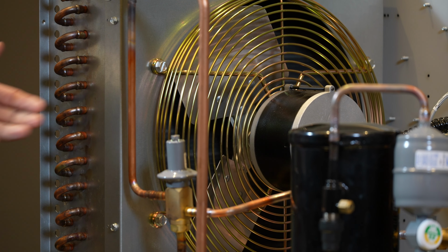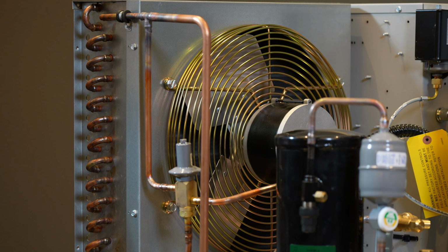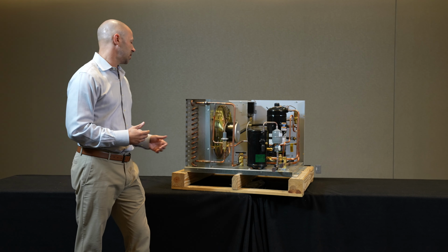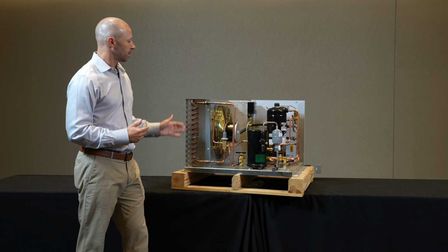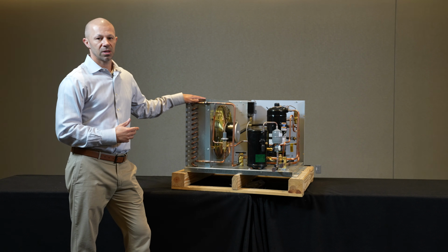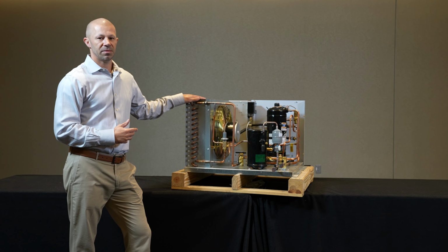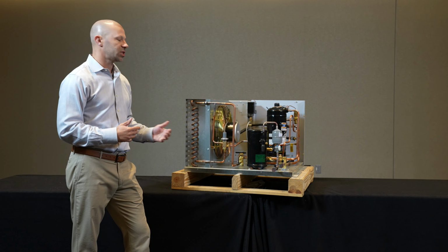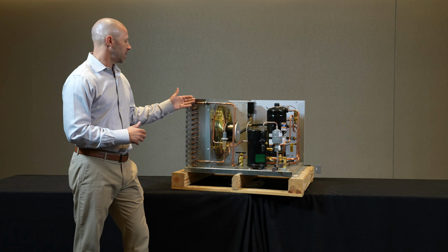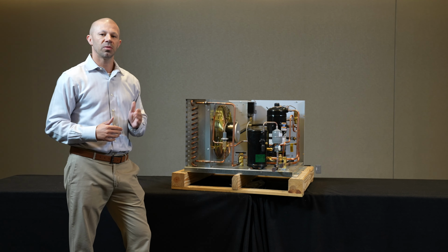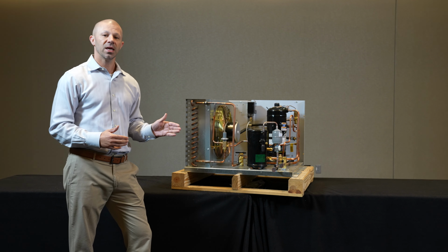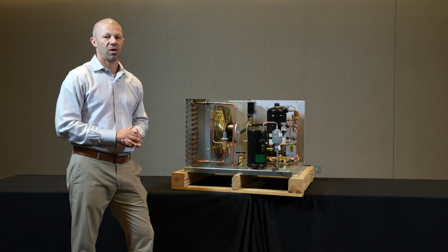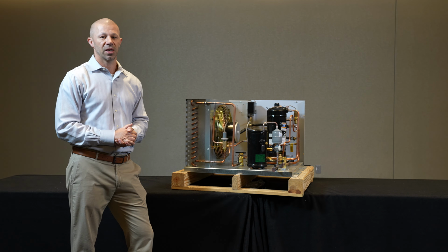Air side control is simply stopping or adjusting the airflow when ambients drop and we do not need the full condenser surface. In a single fan unit, we typically keep this running when the compressor is on because we don't want to thermally shock the condenser coil. But in instances where we have multiple fans, fan cycling at given pressures, turning them on and off as pressures rise and fall, is a standard option on units of that type.